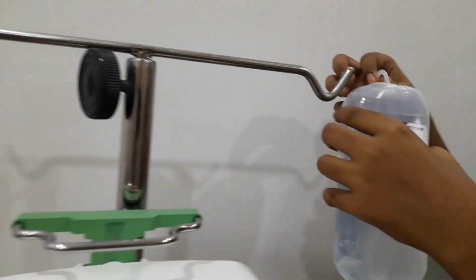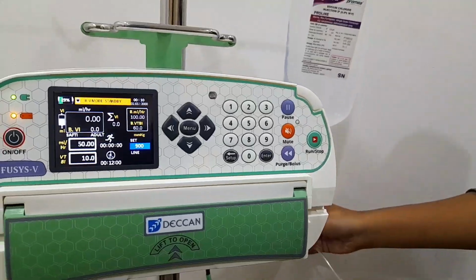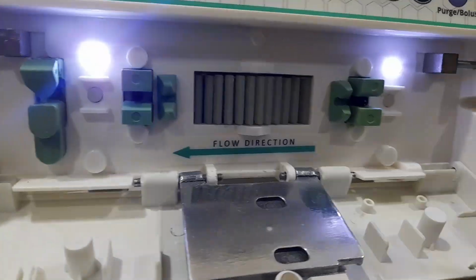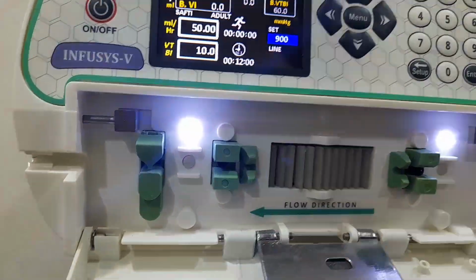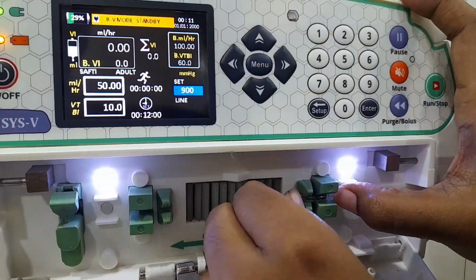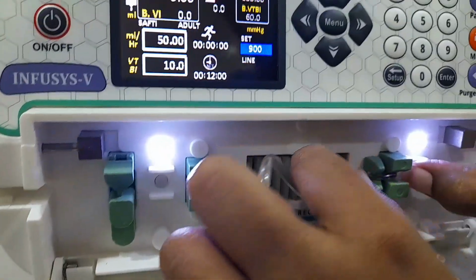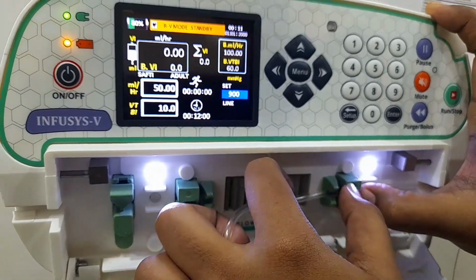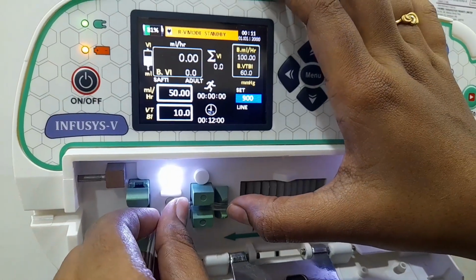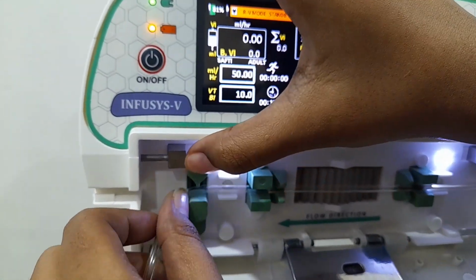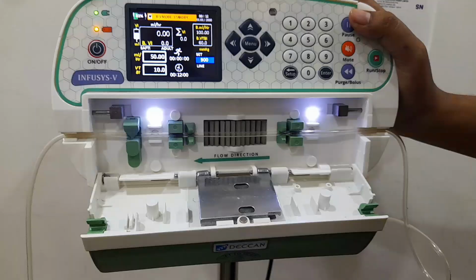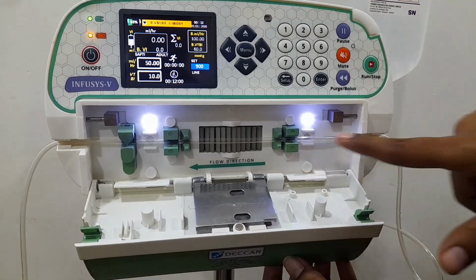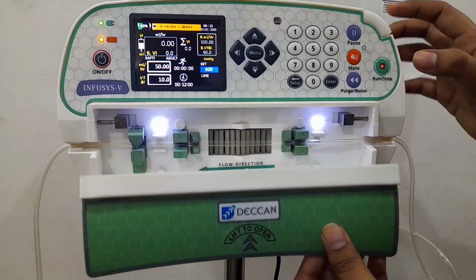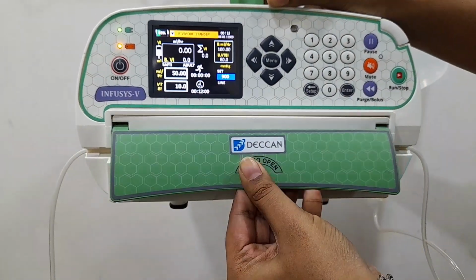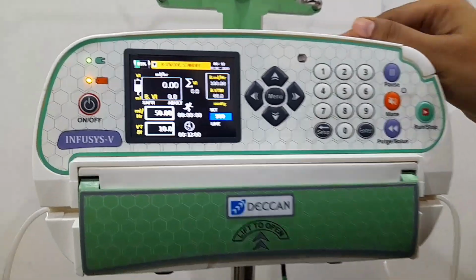Now we can hang the IV bottle to the IV rod. Now connect the IV line by opening the door, through the occlusion sensor, air bubble sensor, and anti-free flow mechanism. Lift the anti-free flow mechanism and place the IV line. It prevents accidental door opening. Once the IV set is placed, check the flow direction. Then we can close the door.